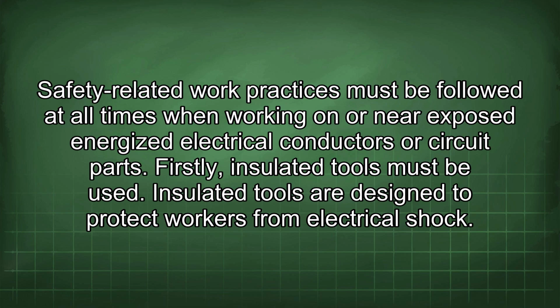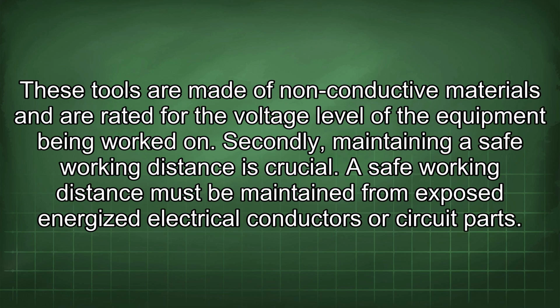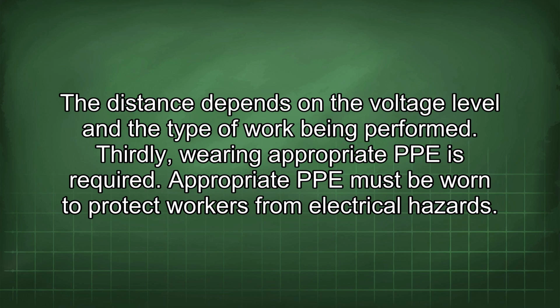Firstly, insulated tools must be used. Insulated tools are designed to protect workers from electrical shock. These tools are made of non-conductive materials and are rated for the voltage level of the equipment being worked on. Secondly, maintaining a safe working distance is crucial. A safe working distance must be maintained from exposed energized electrical conductors or circuit parts. The distance depends on the voltage level and the type of work being performed.